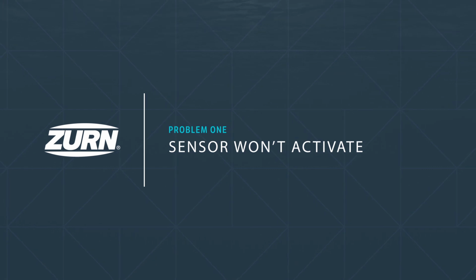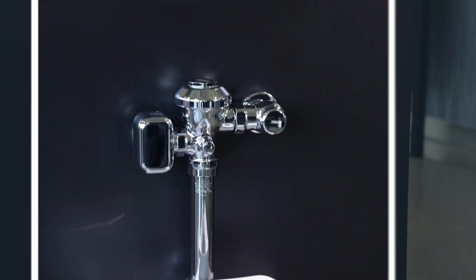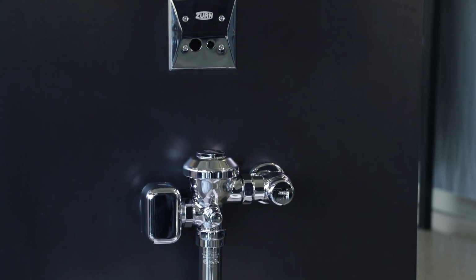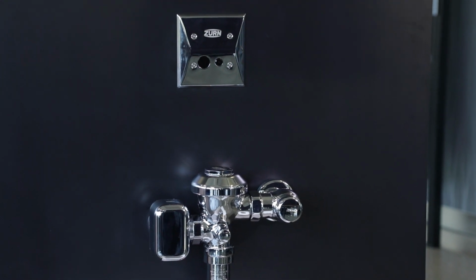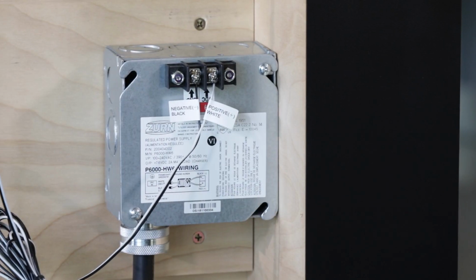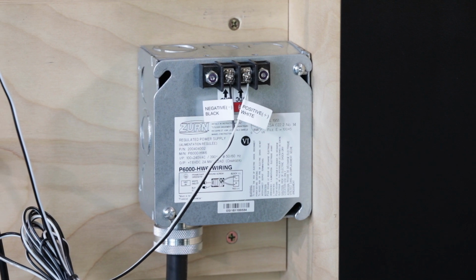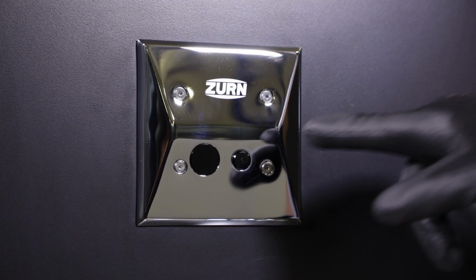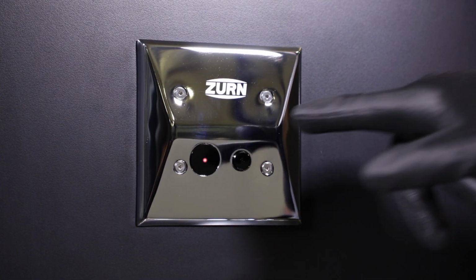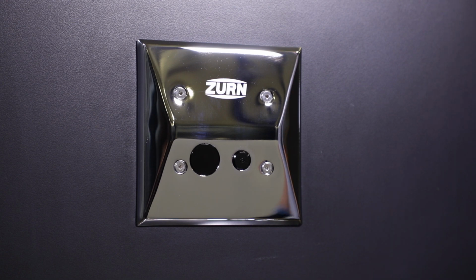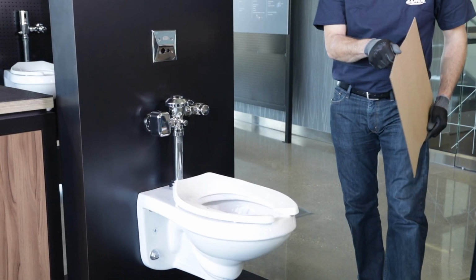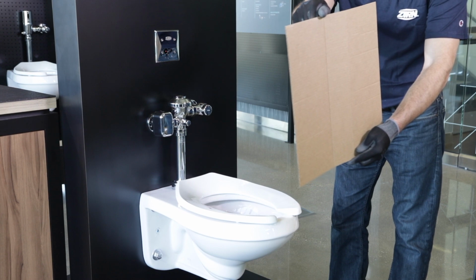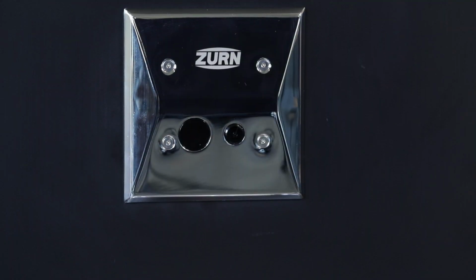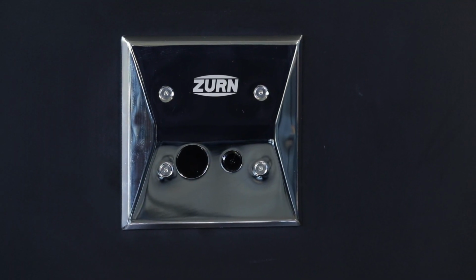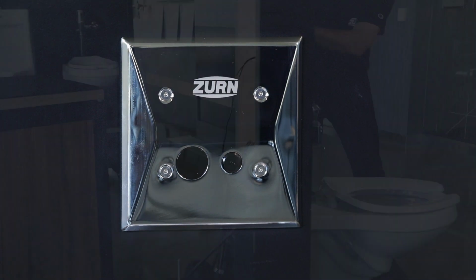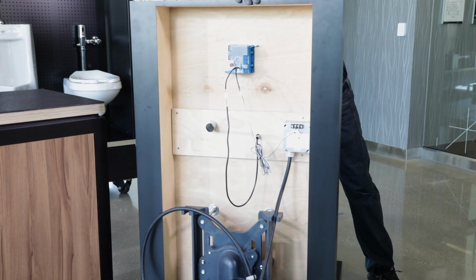The sensor won't activate. So, the flush valve won't activate. There are 2 likely reasons for this. Either the sensor isn't recognizing the user or the power supply is disrupted. First, make sure the sensor works. Press the electronic override button to see if the LED lights up. After that, position a target in front of the sensor, and the LED should light up again. If the LED does not light when you press the electronic override button, confirm the power supply.